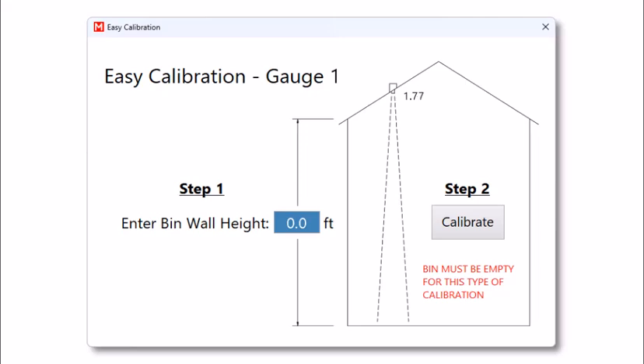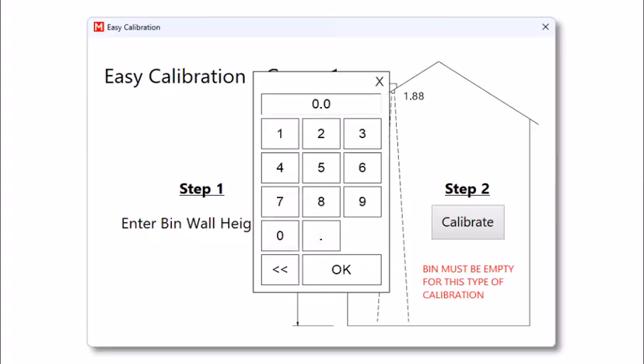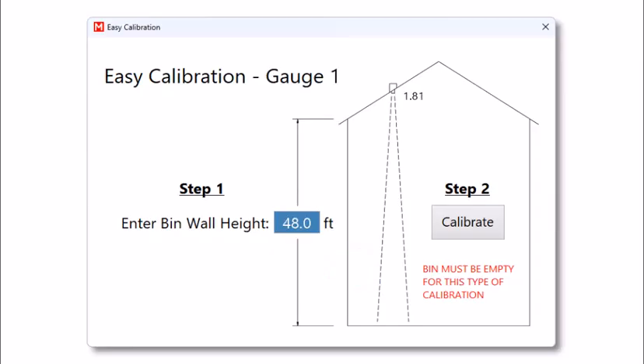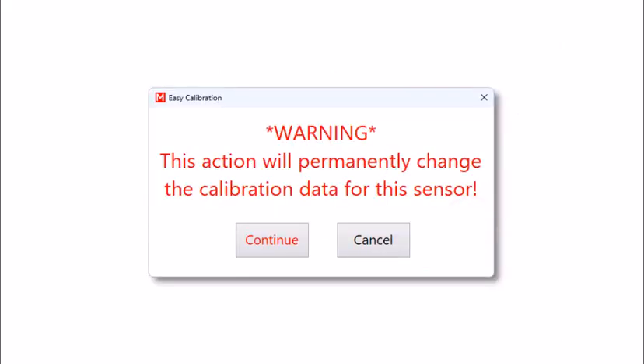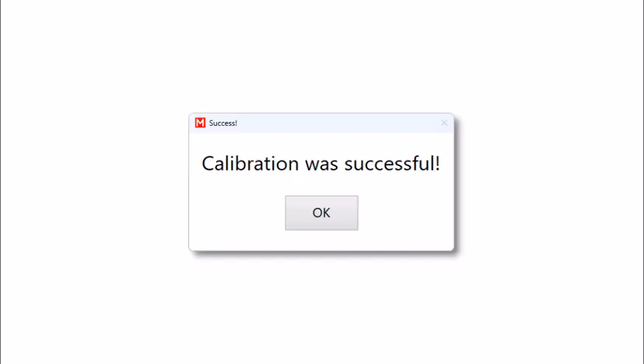Notice the live reading at the top of the bin graphic. This value is showing the distance in feet that your sensor is currently reading. Enter the height of the bin walls by clicking on the blue rectangle and typing in the value on the numeric pad. Hit OK. Now simply hit Calibrate. Acknowledge the pop-up warning since we do want to change the calibration on this sensor. We have now successfully calibrated our sensor using the Easy Calibration method.